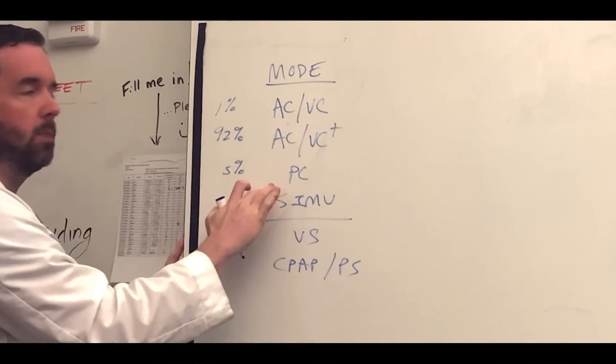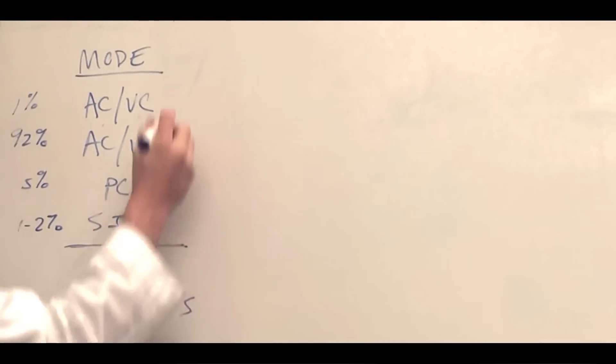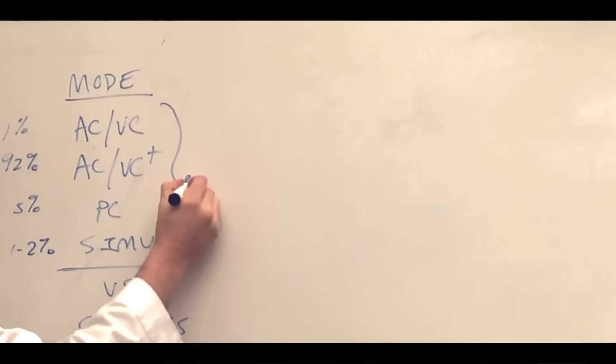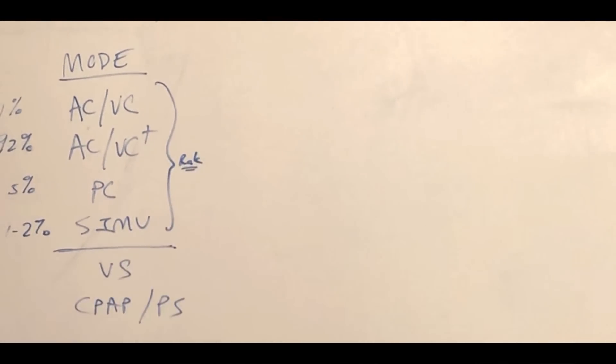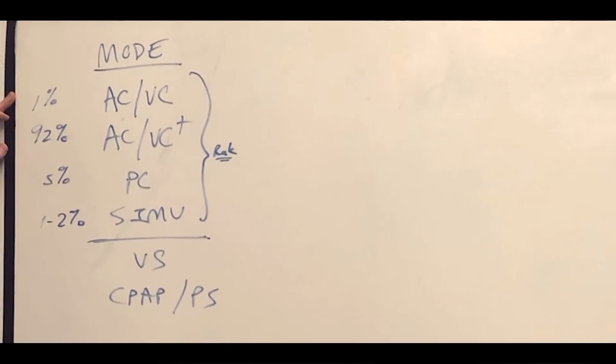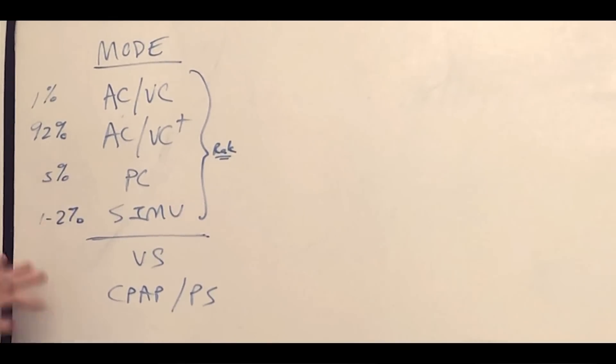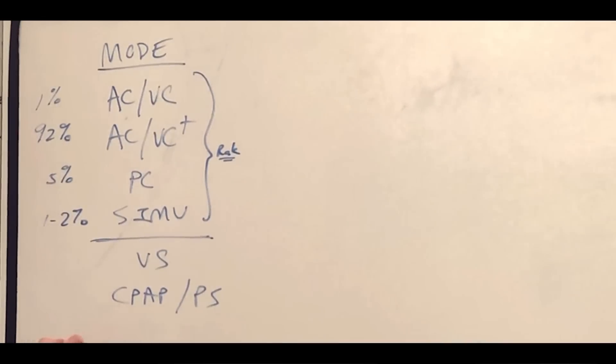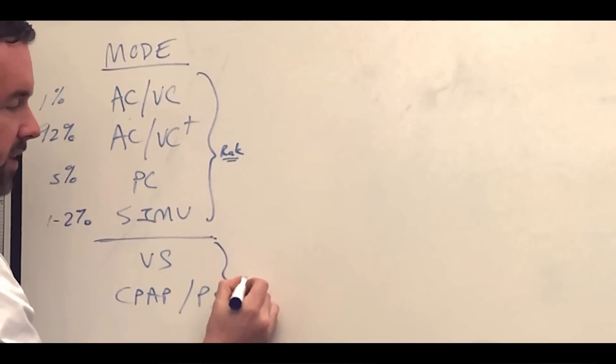These modes up here that I separated with the line, these all involve setting a rate on the vent. So in addition to the mode, you're going to set a rate. The next two, volume support and CPAP pressure support, these are called spontaneous modes.